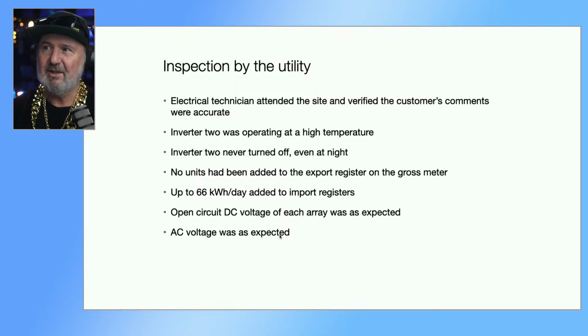The inspection from the utility confirmed all these details, and they noticed that it was consuming 66 kilowatt hours per day. The inverter was consuming 66 kilowatt hours per day doing nothing. And there was open circuit DC voltage on each array, as expected, was correct. So the open circuit voltage on the PV was correct when tested in isolation, and the AC voltage was correct when tested. So some of this looks okay until you start putting a current clamp around the cables.